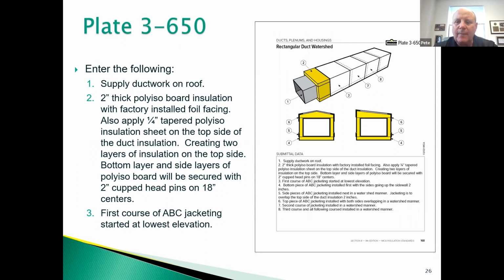Number 1 is always, what type of ductwork is this? In this example, we'll call it supply ductwork on roof. Number 2 is the type of insulation we're going to use—here, 2-inch thick polyiso board insulation with a factory-installed foil facing. I'll also apply a 1/4-inch tapered polyiso insulation sheet on the top side of the duct insulation, creating 2 layers of insulation on the top side. The bottom layer and side layers of polyiso will be secured with 2-inch cupped head pins on 18-inch centers.